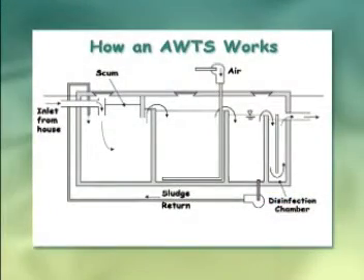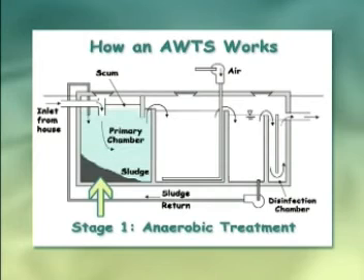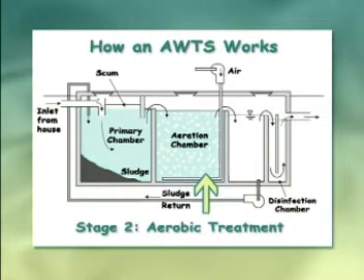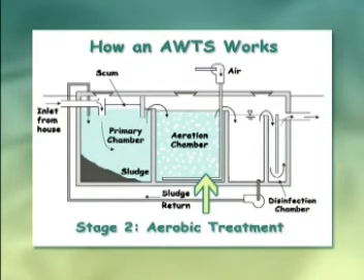Stage one is anaerobic treatment and removes bulk solids similar to a septic tank. Stage two is aerobic treatment, where a large volume of air is pumped into the chamber to promote the growth of aerobic bacteria, which efficiently and quickly break down and consume the remaining waste products. Some systems use electric pumps and air blowers, and some have an external in-ground sand filter as part of their treatment process.